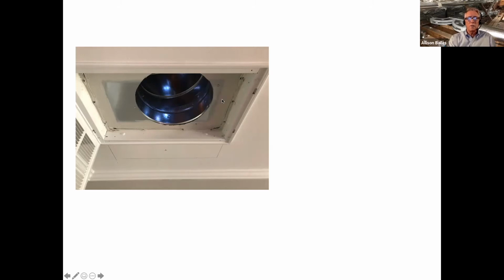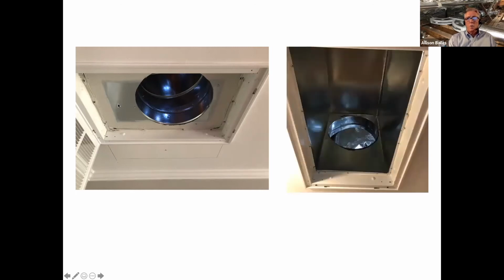Although the filter did look uniformly dirty, so some of it was going through the edges, if I'd left it longer, I probably would have had a nice round circle of dirt in the filter. You need space behind the filter, and ideally you want about 6 inches of space. So I had this retrofitted. I had this piece of sheet metal taken off, and I had a big box put on the backside. So this is way more than 6 inches. I got about 20 inches, I think.